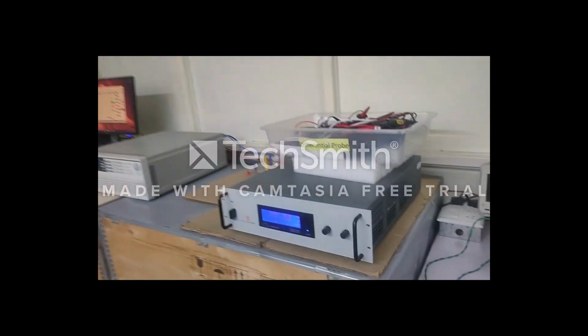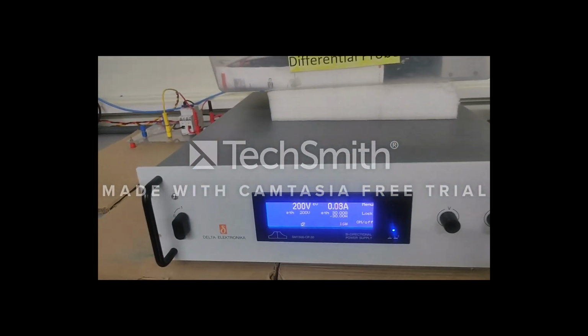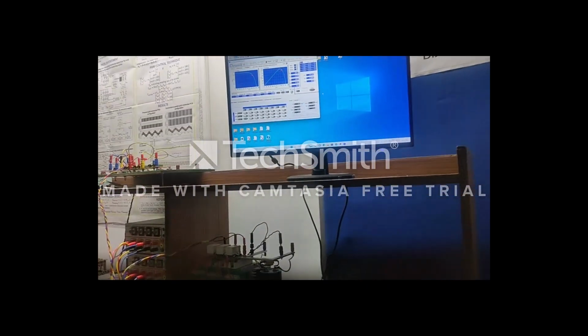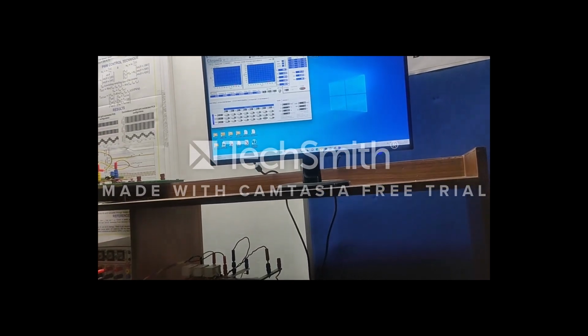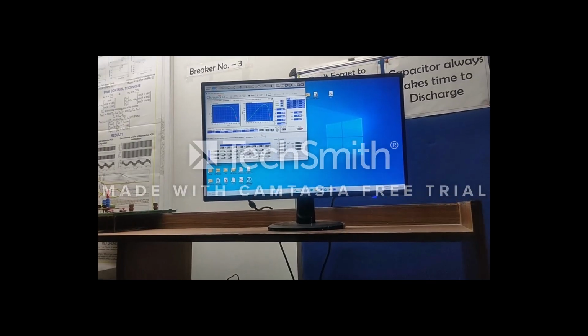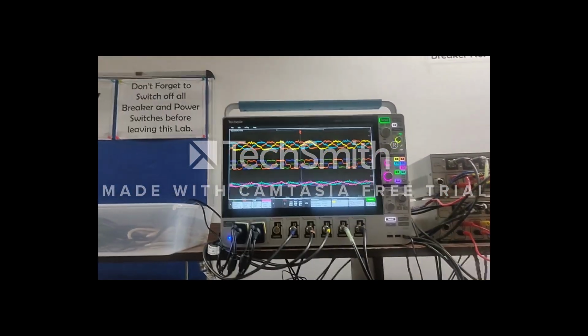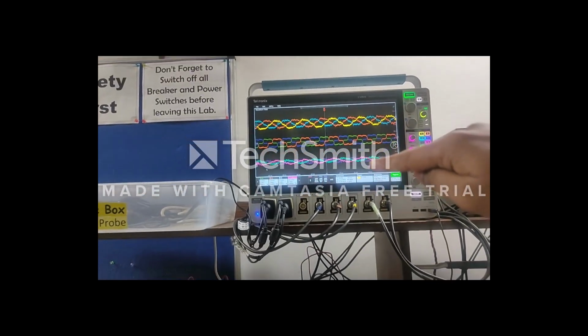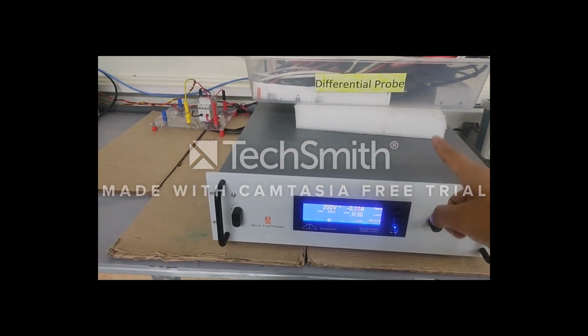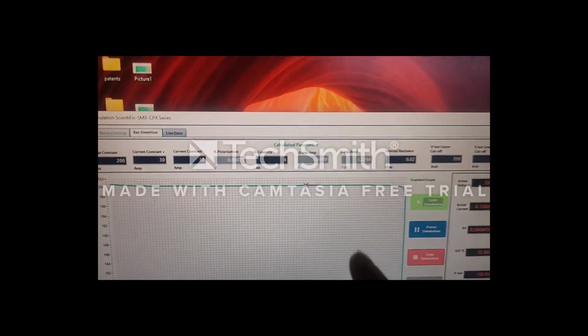Now we change the irradiance. Here you can see the battery is not giving any active power, it is only compensating the harmonics. Now if we want to inject active power from the solar inverter, by changing the irradiance, I am now changing it from 5% to 75%. So it starts tracking the new MPP point on the PV curve. You can see the red point moving to the top. You can see in this curve, the inverter power is more than the load power, so it starts injecting into the grid. You can also see the battery: whatever extra power is available at the inverter, it starts injecting into the grid. The battery starts charging. You can see the battery SOC is increasing from 30% to 35%.